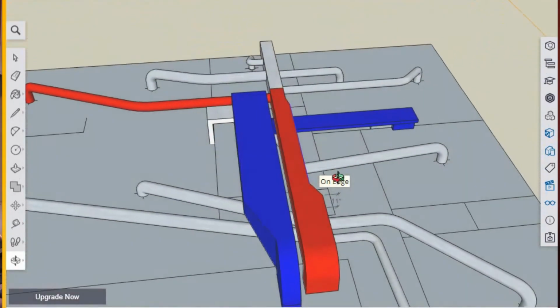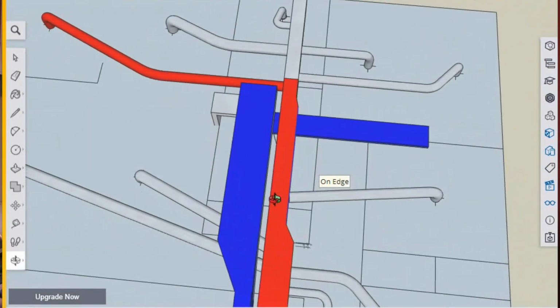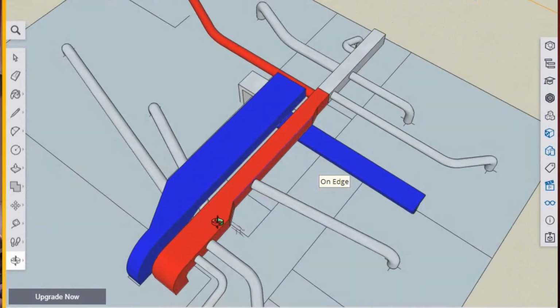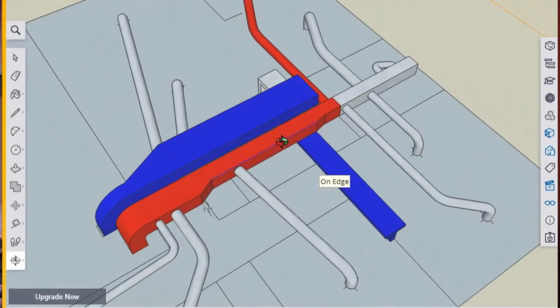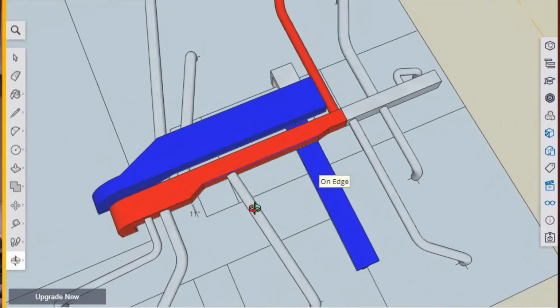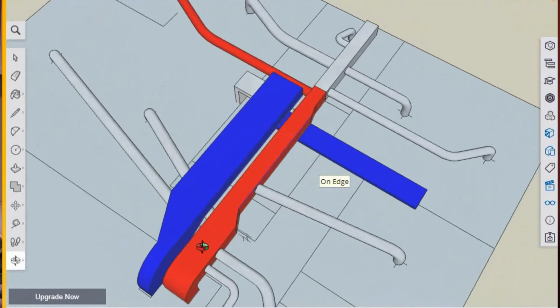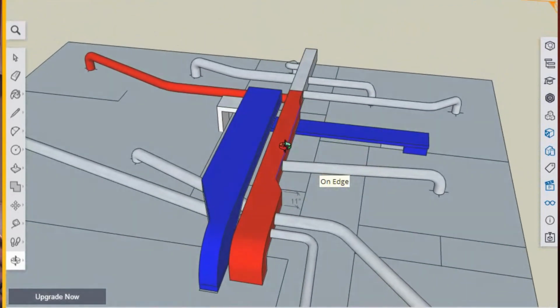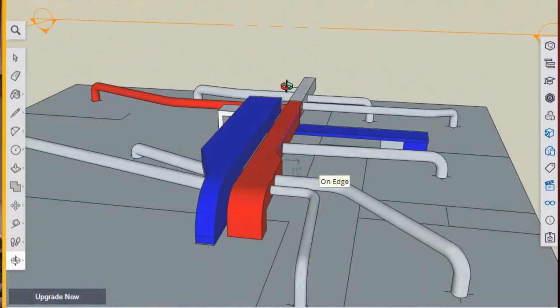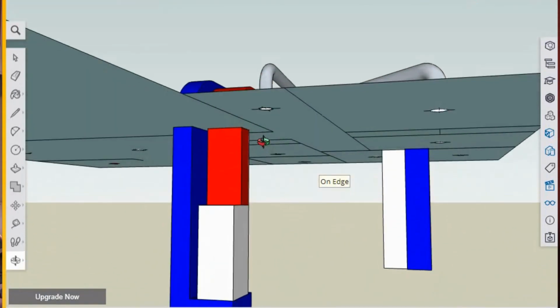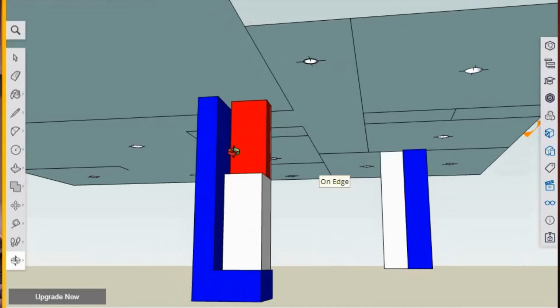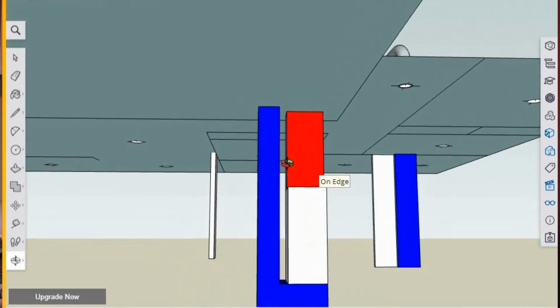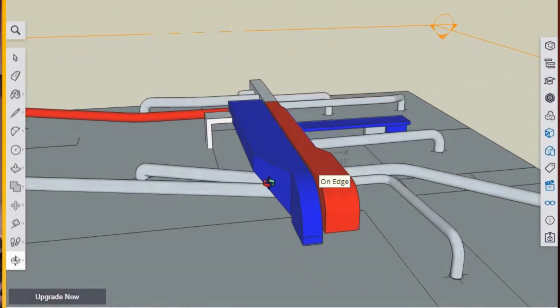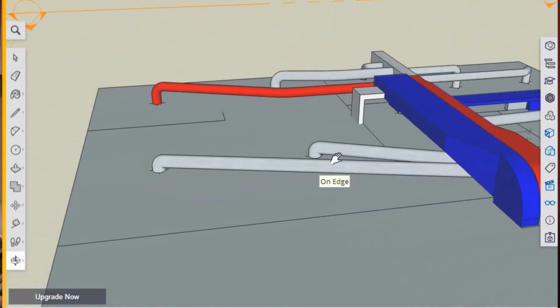Now, setting the system up this way will give us great airflow. It'll give us the ability to correctly damper everything off and balance everything, and will give us a system that will last a very long time. It'll keep our pressures within the system relatively low, and the static pressures within check for the blower, and keep our air flowing in the way it should be flowing. So that's how we would do that.